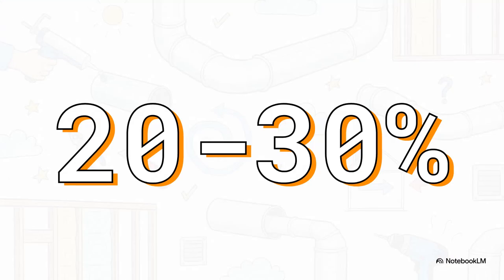Now, what's really interesting about this is this massive number right here, 20 to 30%. That is the amount of energy and, honestly, your hard-earned money that can be completely wasted by duct leaks in the sweltering Tampa heat. If your ducts aren't sealed to our rigorous protocols, standard practices are gonna fail you, and you will literally be paying a 20 to 30% premium on your utility bill just to cool off your attic space? No way we're letting that happen.